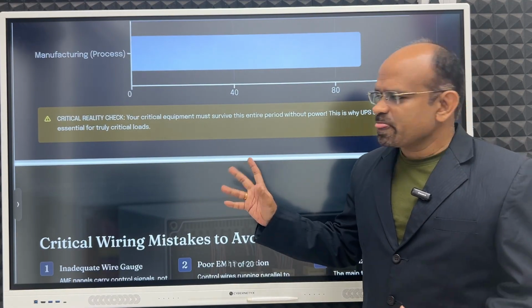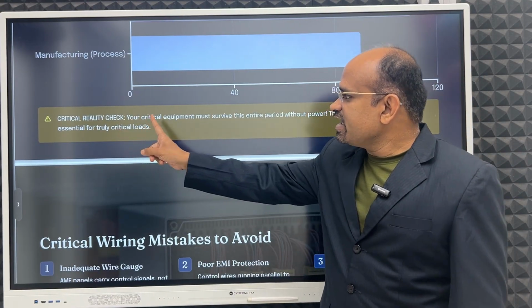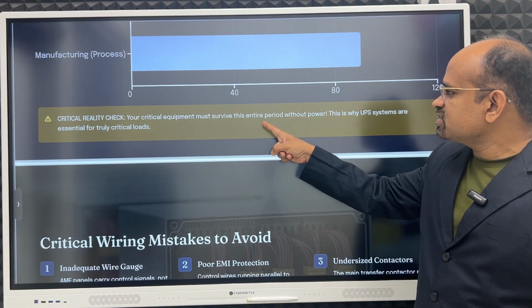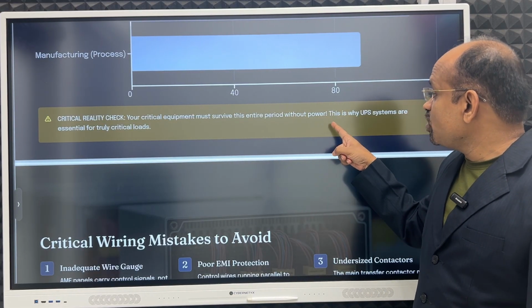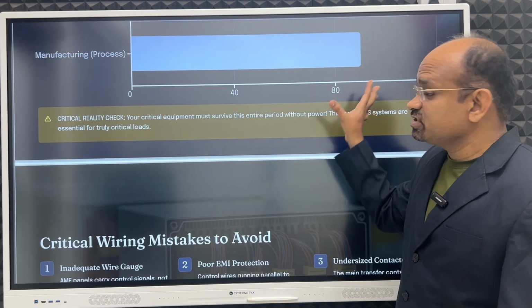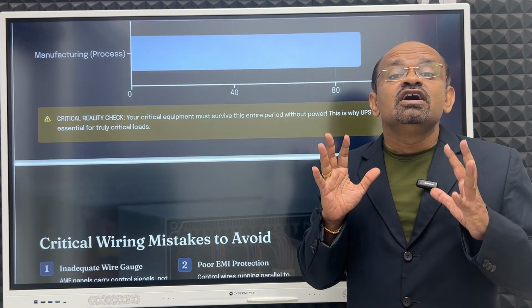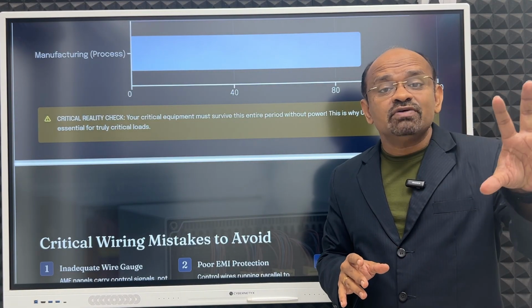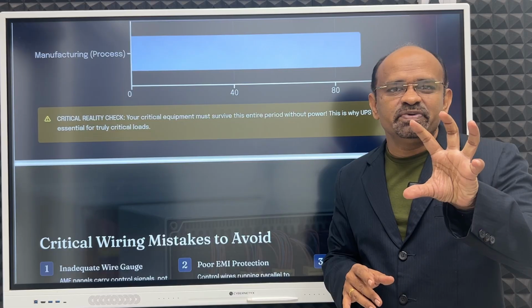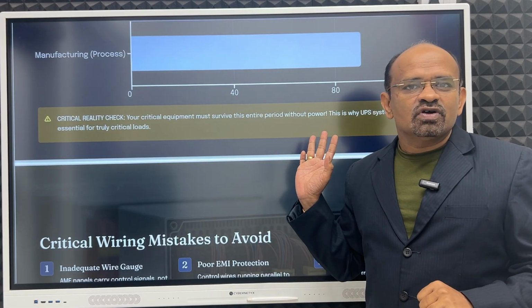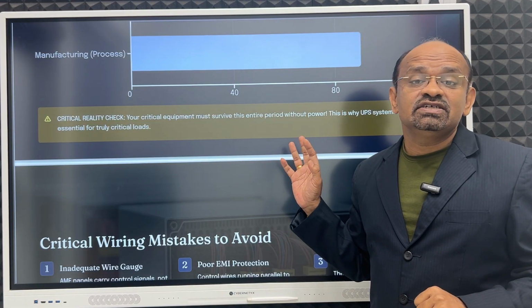Generally, a critical reality check: your critical equipment must survive this required period without power. This much your critical equipment should survive. For that, we should have a small UPS for the critical load. Otherwise, it must survive on its own.